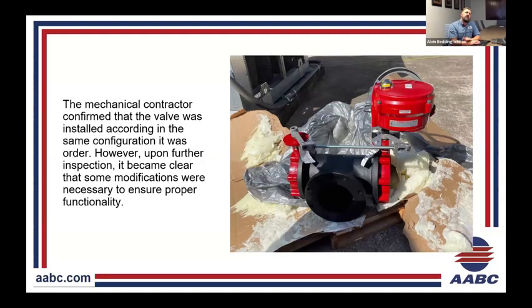So basically, talking to the mechanical contractor, he confirmed that the valve was ordered the way it is. This is how I got it. This is exactly how it was configured. And talking with him and trying to explain that the water's going to go in, if they're tied together, you're either both open, both closed, or vice versa. You could be open and closed, but either way, water's not going to make it through that pipe to get back to the tower, and we're going to keep losing flow.